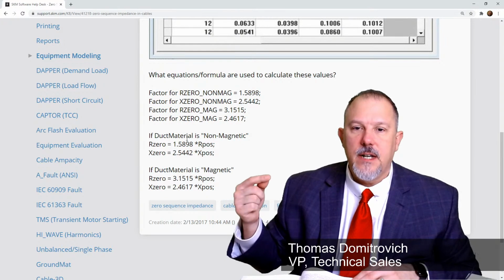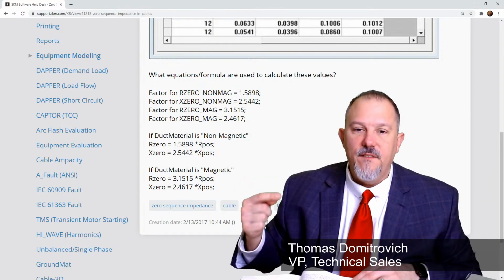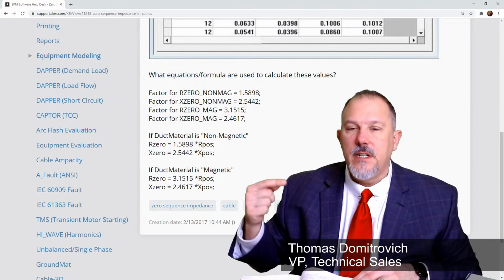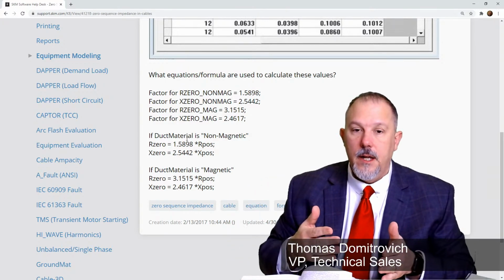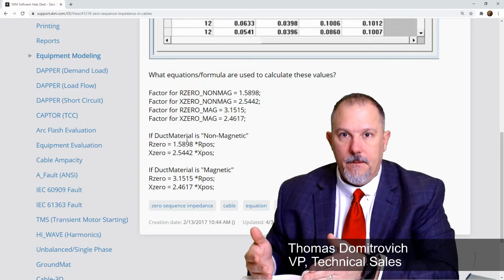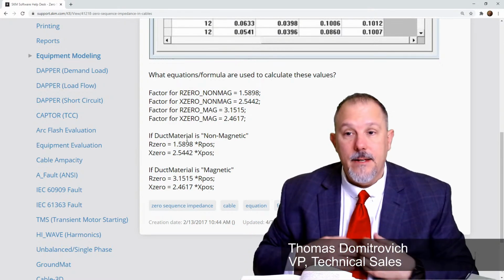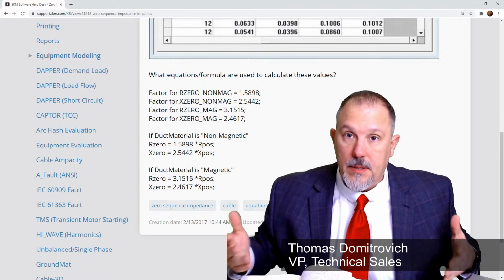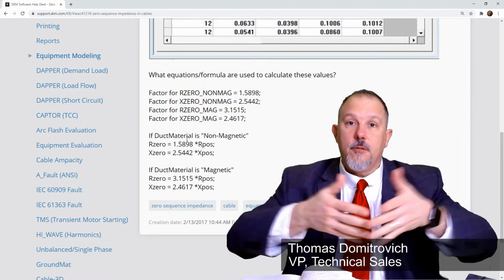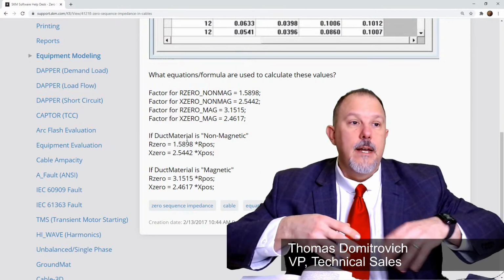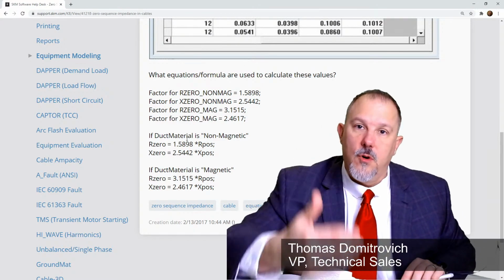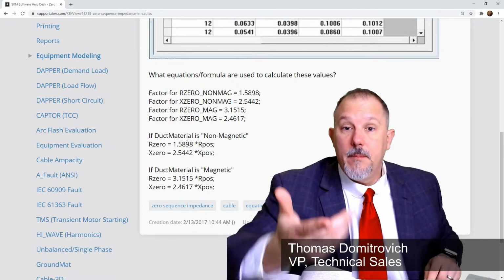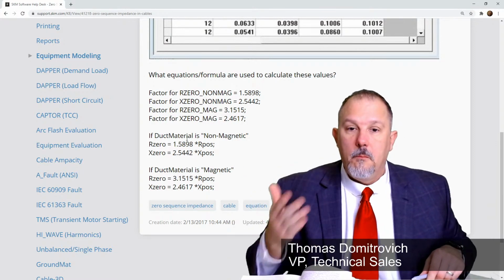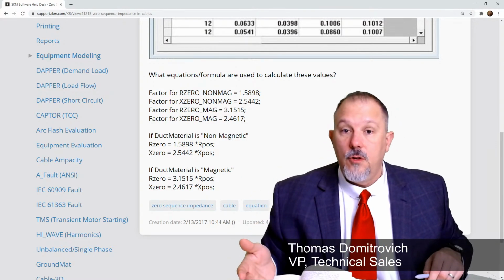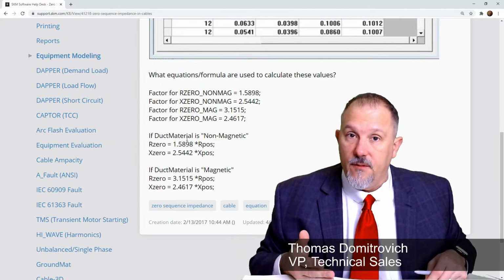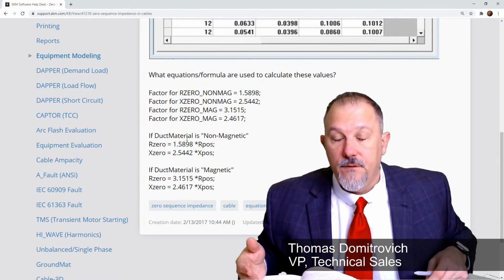1.5898 if it's non-magnetic, 3.1515 if it's magnetic, and they give a different multiplier for the resistance than they do the reactance. Historically, what I've always done was just do 3 times the impedance, because I've got 3 different currents. They're all in the same phase, and I would multiply the impedance by 3 times. But based upon this, when you break down the R and the X, you multiply the R by 3.1515, you multiply the X by 2.4617.